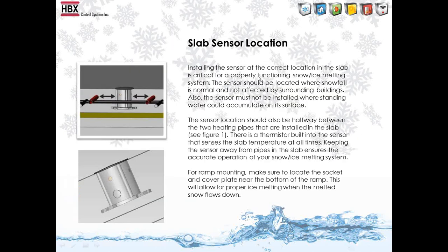For slab sensor location, obviously you don't want to be too close to the pipes in the slab, as it will affect the sensor reading. If you have located the sensor too close to one of the pipes, you'll get a bad slab reading. In that case, you could use the remote slab sensor technology built into this, so that you can take the slab reading from another location. You don't necessarily have to use the slab reading in the actual sensor. And for ramps, you want to be down at the bottom of the ramp where the water would collect and turn to ice.